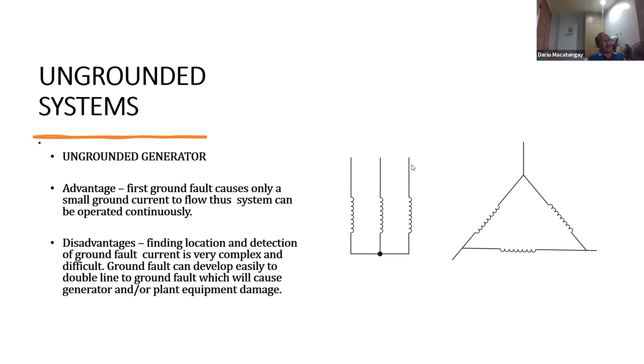It's static electricity, right? So now, when you have a ground fault here, you might wonder, even if I have a ground fault here, I don't have continuity. Well, you still have because of the capacitance to ground, but that's very small, so it's tolerable. When you have a ground fault in an ungrounded generator, it will not trip right away. But the problem is that the voltage on the healthy phases will increase and subject those healthy phases to insulation damage and will cause a double line to ground fault, which is destructive.